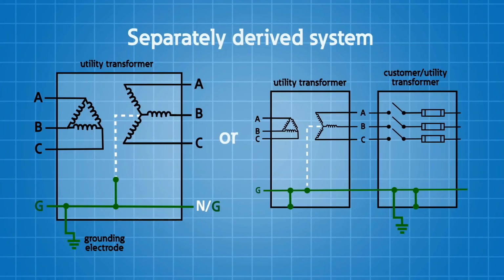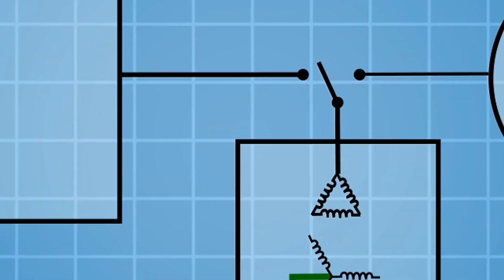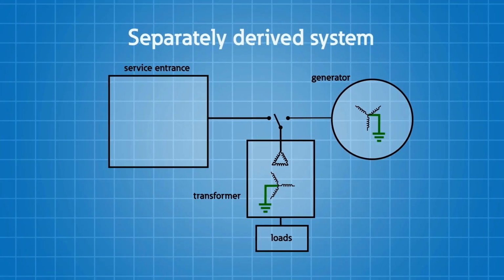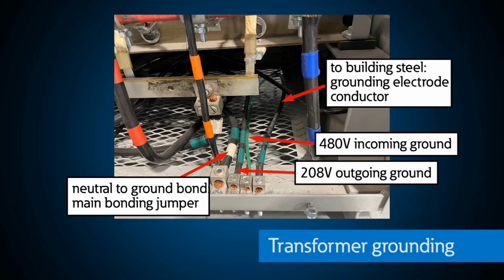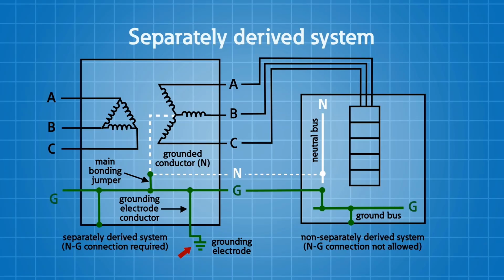Think of a separately derived system as a point downstream of the service entrance equipment where electrical isolation creates a new source. Usually, this is a new transformer connection or perhaps a generator. In either case, a new grounding and bonding scheme is required for this separately derived system. Here's an example of a separately derived system with delta Y 3-phase transformers. Here is the grounding electrode conductor and the main bonding jumper. This establishes the grounded conductor that we talked about in the previous section.